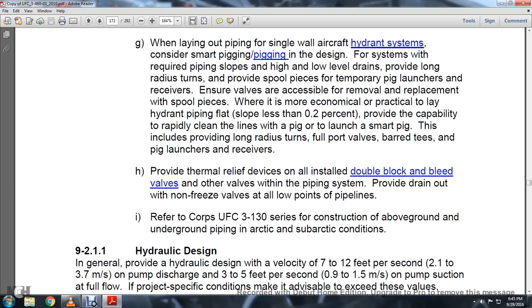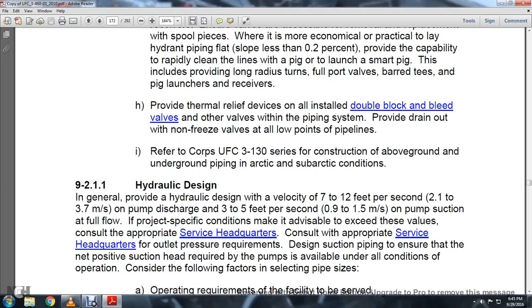9.2.1 Hydraulic design. In general, design hydraulics with a velocity of 7 to 12 feet per second on the pump discharge and 3 to 5 feet per second on the pump suction as full flow. The project specification conditions may make it advisable to exceed these values. Consult the appropriate service headquarters with outlet pressure requirements. Design the suction piping to ensure that the net positive suction head required by the pumps is available under all conditions of operation.